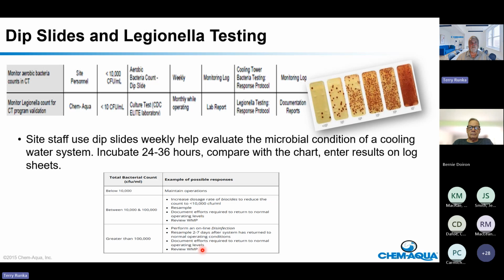The actual number industry says you can have before you even have to worry about it is 100,000 colony forming units - not Legionella bacteria, total aerobic bacteria. You're aiming for less than 10,000, which is 10 to the 4.